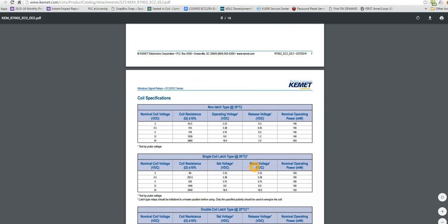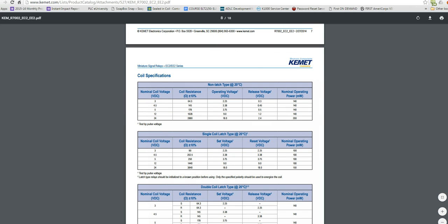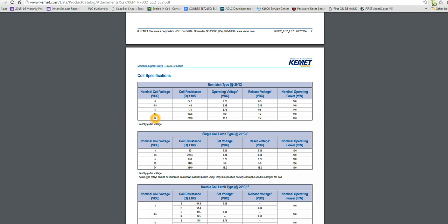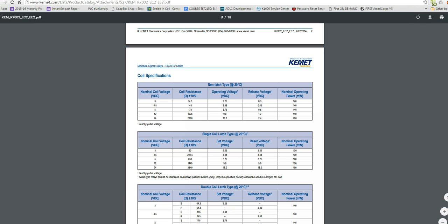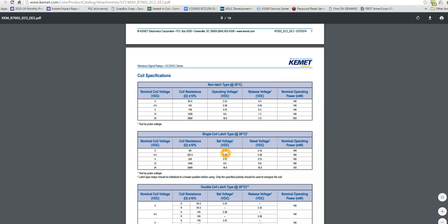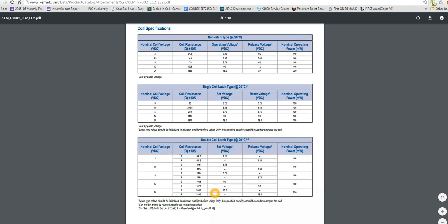Here's the coils. Now it depends on which relay you've got, which coil you have. So let's say we chose a 24 volt coil we've talked about before. The 24 volt coil has a resistance of about 2,800 ohms. It will operate at 18 volts. Even though it's a 24 volt coil, it'll operate as low as 18 volts. And it'll release when the voltage is less than 2.4 volts. And that's for the non-latching relay. And then specifications for the latching relay and the double latching relay as well.